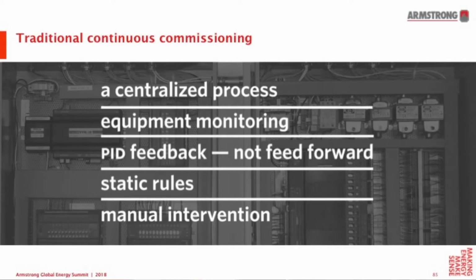There are other problems with continuous commissioning. It's a very centralized process—most building owners who venture into it need building automation systems, the building management system that Peter mentioned. It's also based on a lot of monitoring, but most importantly, it's based on static rules and human intervention, and that adds time, and time is something we don't have when addressing the drift in the white space Peter mentioned.